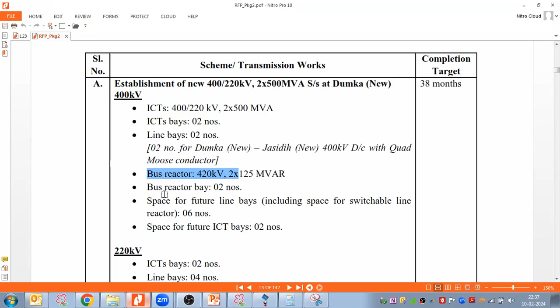And they are putting the reactor, connecting the reactor to their bus bar, and that is the reason they are calling this reactor a bus reactor. If I'm putting the reactor connected into the line, then I will call this reactor a line shunt reactor. Please note down that terminology as well. So bus means connecting on the bus; if I'm putting the line shunt reactor, it means it will connect to a particular dedicated line.